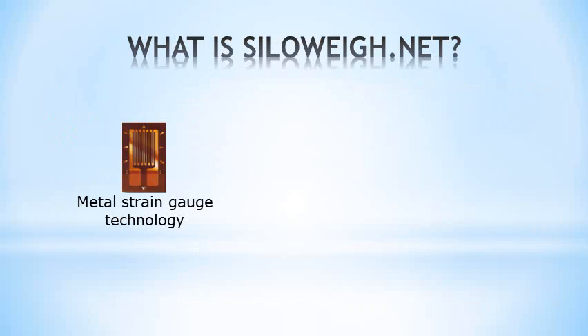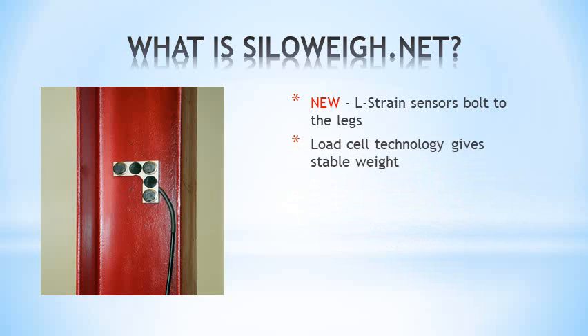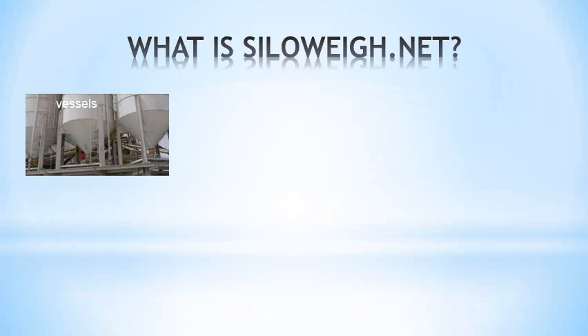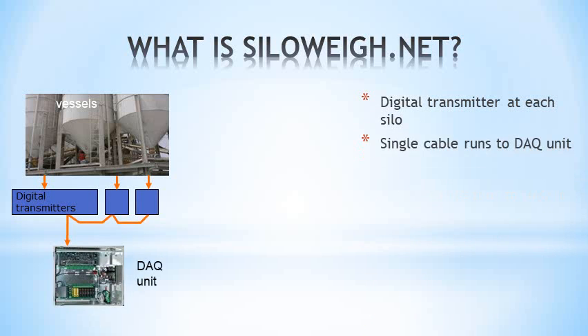SiloWeigh.net uses L-Strain sensors on each vessel leg. The sensors use load cell technology to accurately measure the stress in the legs, which is related to the weight in the vessel. The results are displayed on any computer in the local network. The sensors are connected to digital transmitters that are daisy-chained through a single cable to the DAQ unit, which stores the data.